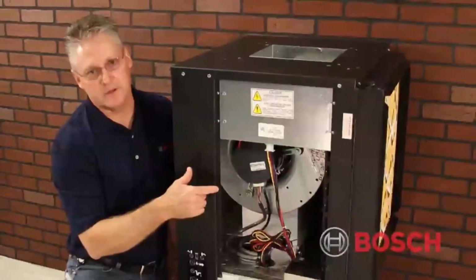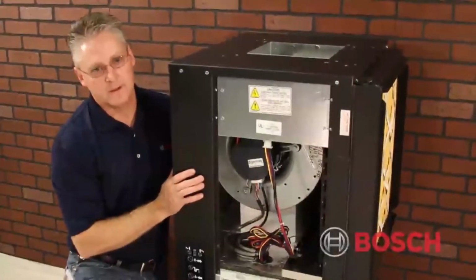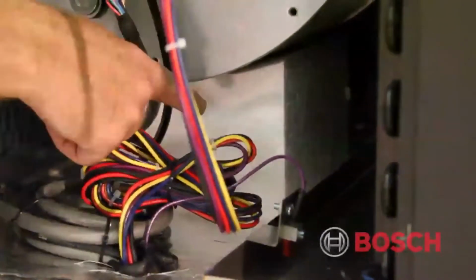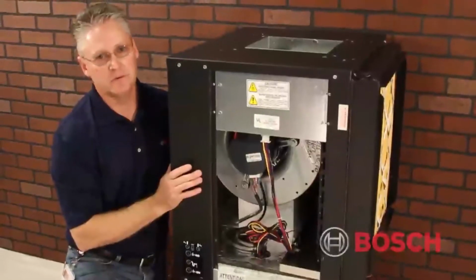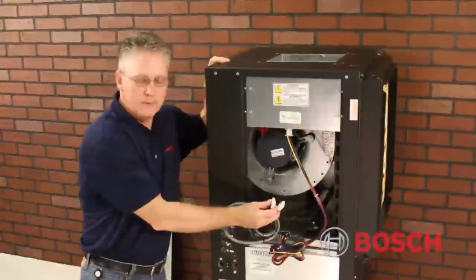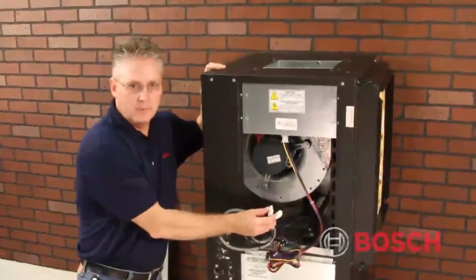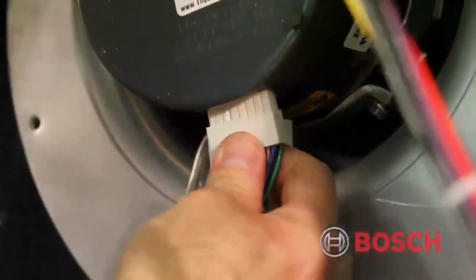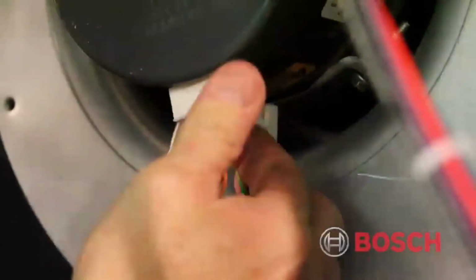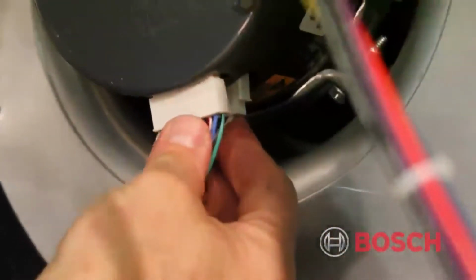Inside the blower compartment is the ECM drive blower motor. It is protected in shipping by the styrofoam shipping block. It must be removed upon installation. I removed the Molex plugs from the ECM drive blower motor to make the styrofoam block removal easier. Now I'm going to replug these back into the ECM motor.